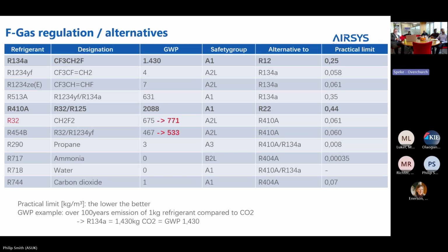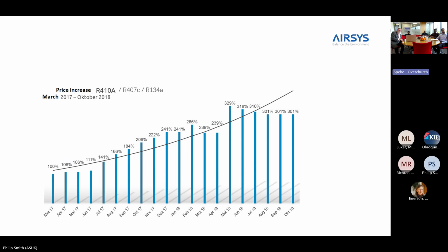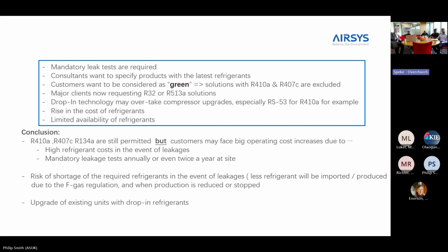So at the moment, the manufacturers of the refrigerants are having to develop and redevelop a refrigerant with a lower GWP that could still be used on the same basis. The problem that we have is that if you have a low GWP refrigerant that isn't flammable, a 40 kilowatt unit becomes a 25 kilowatt unit in the same space because its efficiencies are such. So it has lots of knock-on factors which are affecting the industry in general. And unfortunately, refrigerant prices are rising, and we have everyone on our back from the Green Brigade onwards.